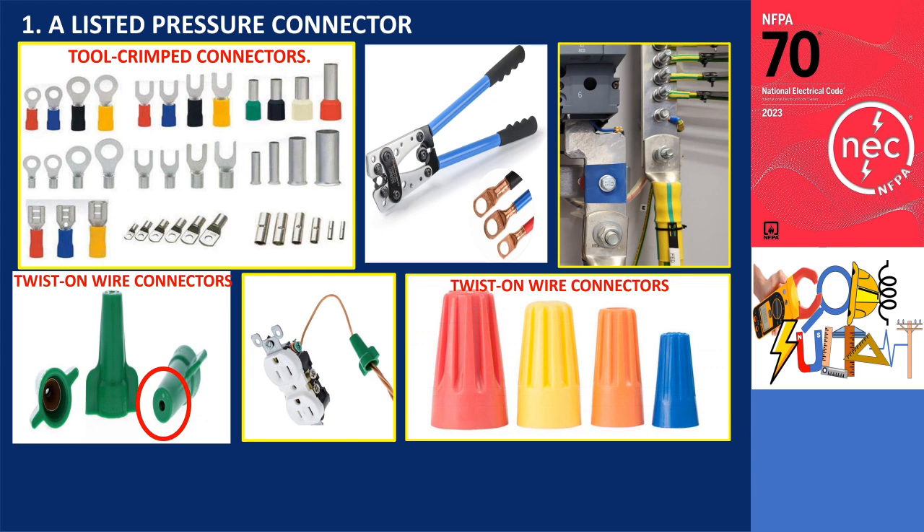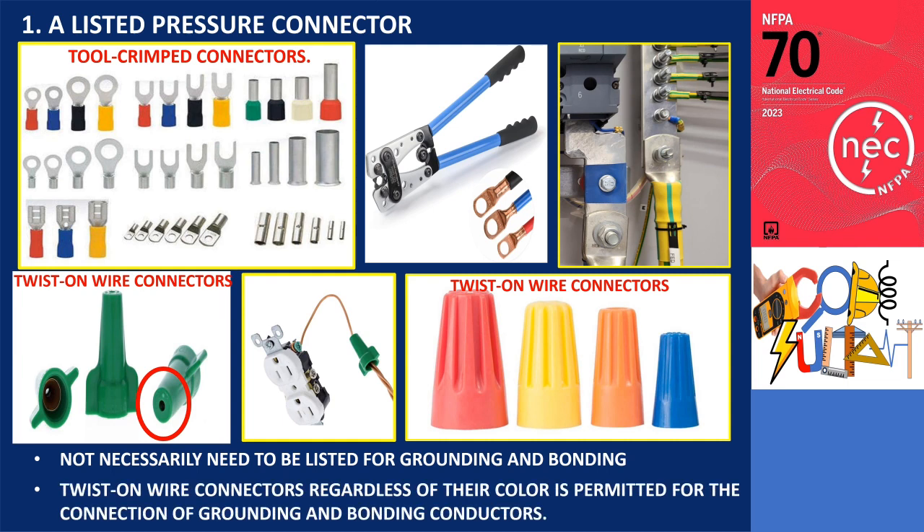Further, conventional twist-on wire connectors, commonly employed for splicing equipment grounding conductors, are also included within this category. It is important to note that these connectors do not necessarily need to be listed for grounding and bonding purposes. The use of twist-on wire connectors, regardless of their color — excluding the green ones with a hole at the top — is permitted for the connection of grounding and bonding conductors.